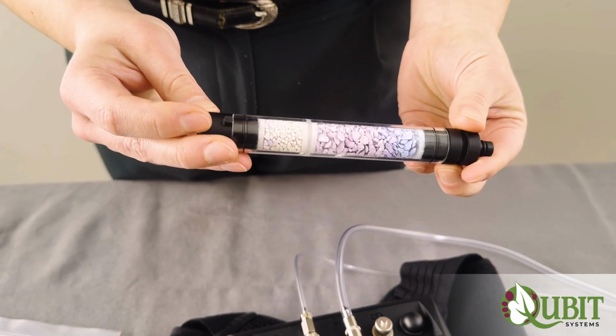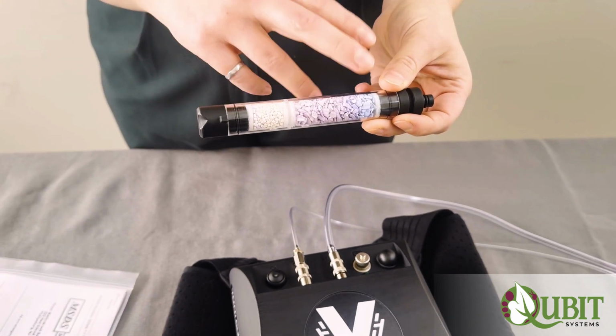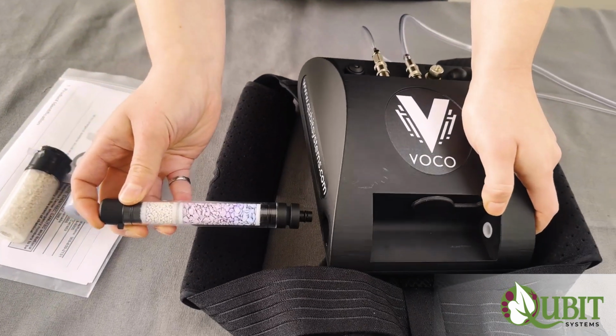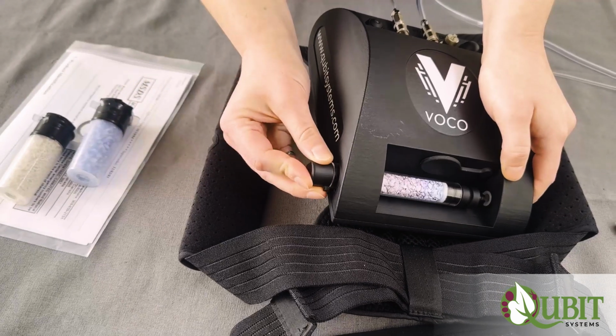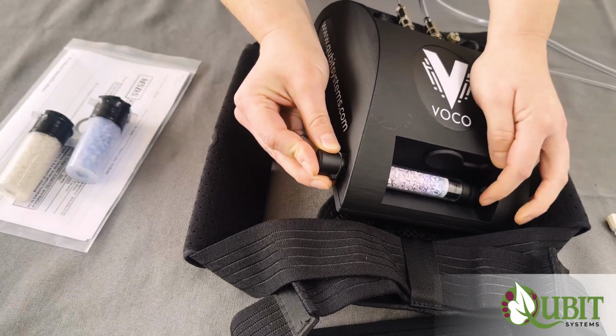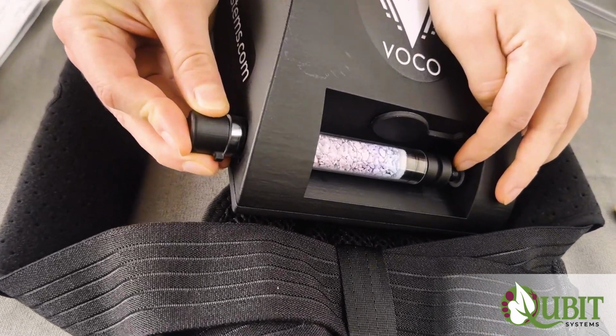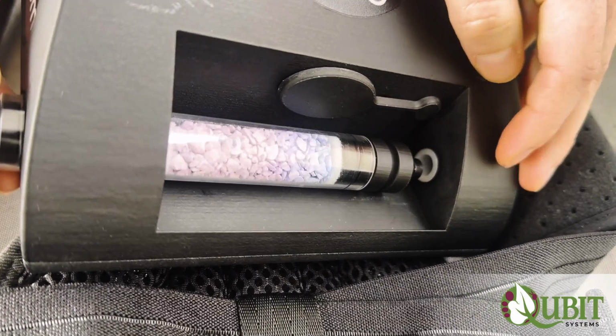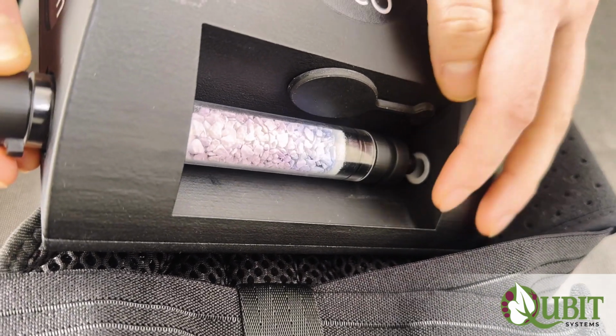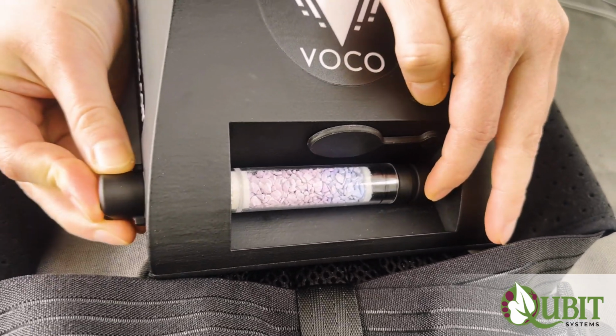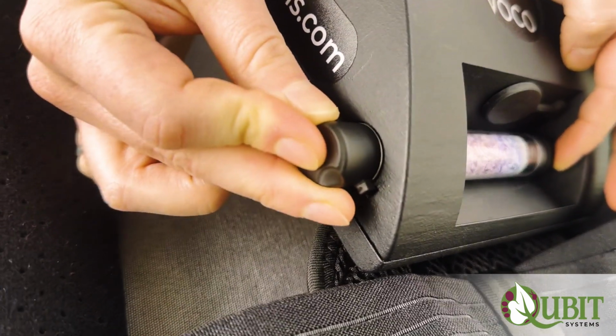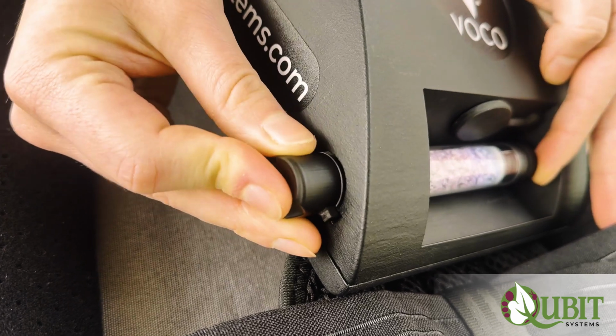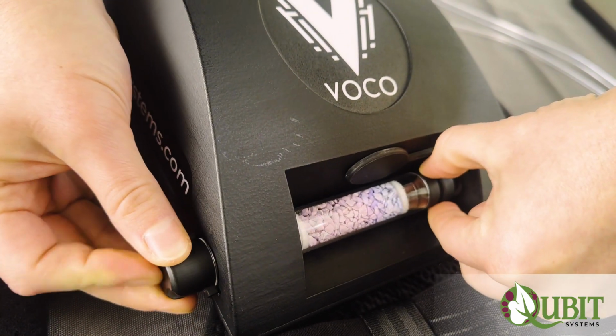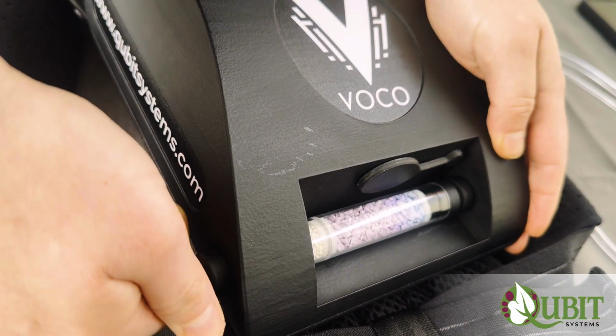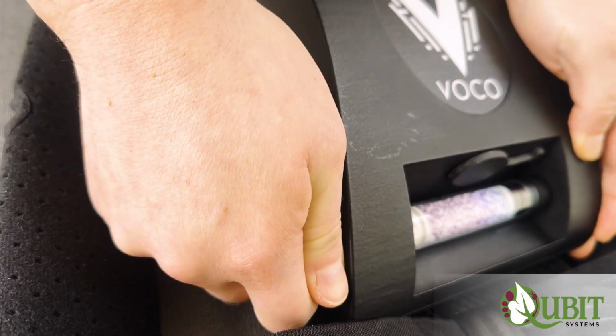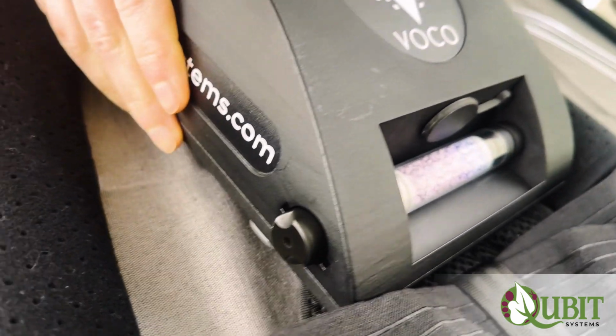And now, let's assume that we've replaced both chemicals and we want to put the tube back in the VOCO. Line up the end of the calibration column here with the hole in the VOCO, and line up the tabs on the side of the VOCO, and let's put it here, and then push, and then rotate clockwise to close the column.